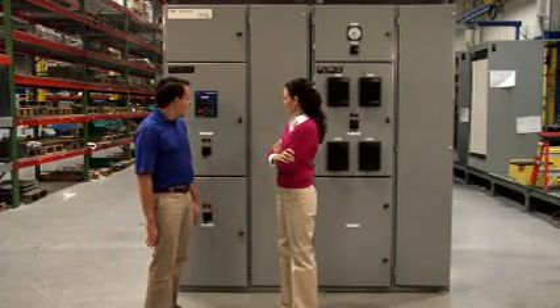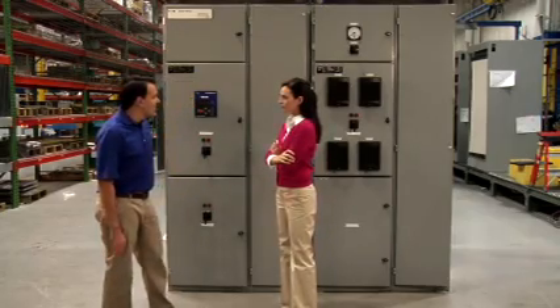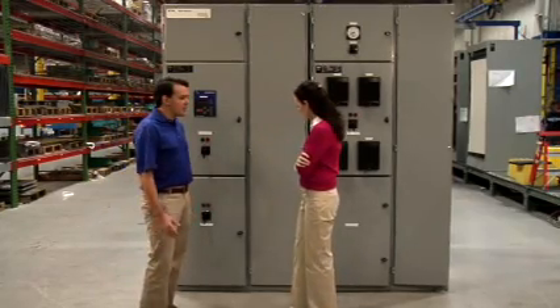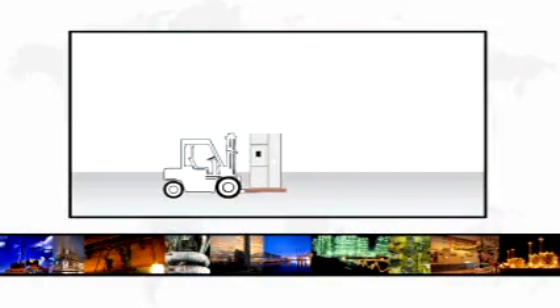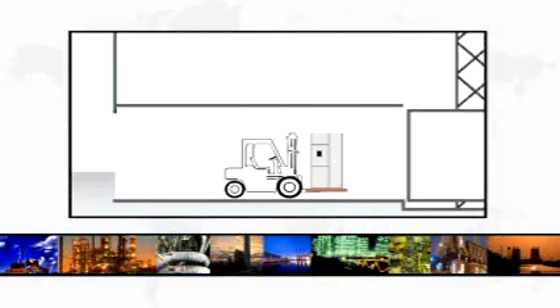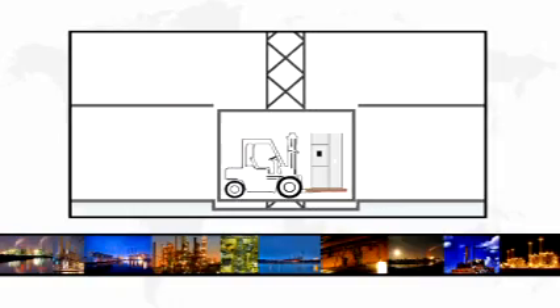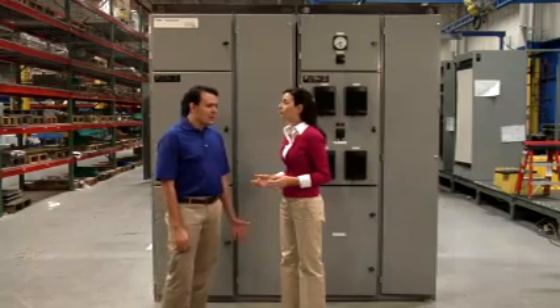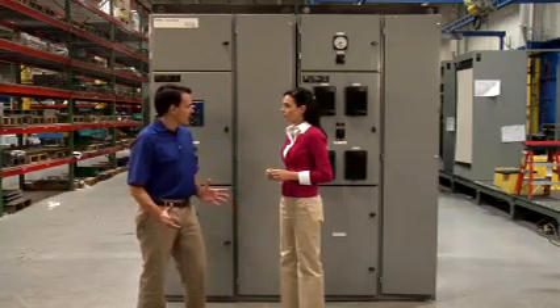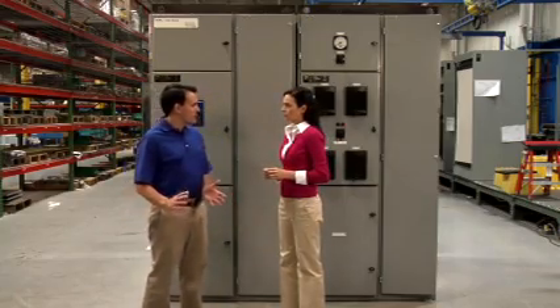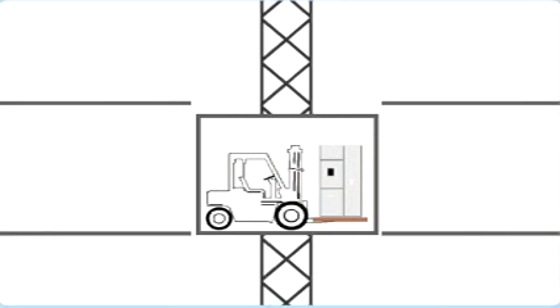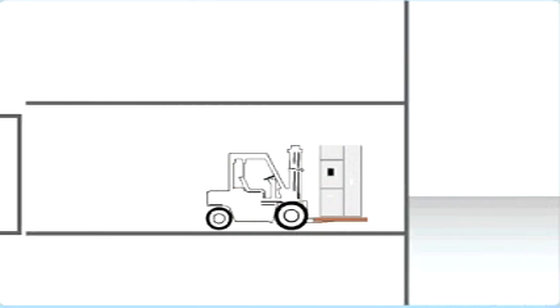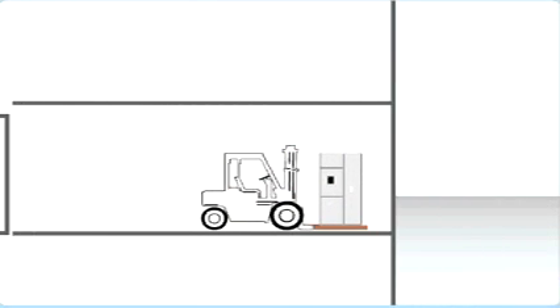small it is. If you just take a look at it, it's about half the size of a traditional piece of metal-clad switchgear. You can actually pick this up with a fork truck, drive it across the plant, load it onto a standard shipping truck, and fit it into a freight elevator once you get on site. And that's got to reduce the cost of shipping, right? Absolutely. And not only the cost of shipping, but once this piece of gear gets on site, it reduces the need for overhead cranes because you can roll right up with a fork truck, pick the gear up, and maneuver it into a tight space in a control room.